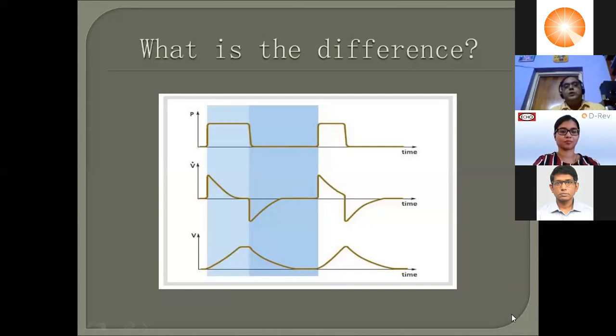And as you look into the volume curve also, look here, because we have a zero flow state, so we have this plateau phase and then the expiration. Here you do not have a zero flow phase, so you do not have this plateau. So it goes up and then drops down straightaway. So in a supported breath, the time will be less, the flow will never reach the baseline. On the volume curve, you will not have the plateau. This is how a supported breath looks like. Next one, please.